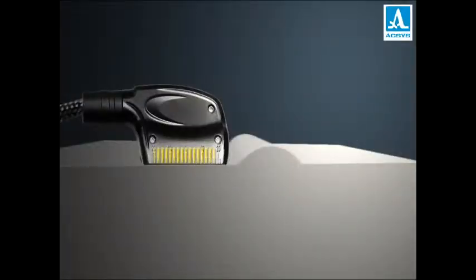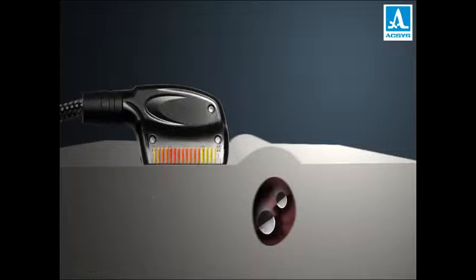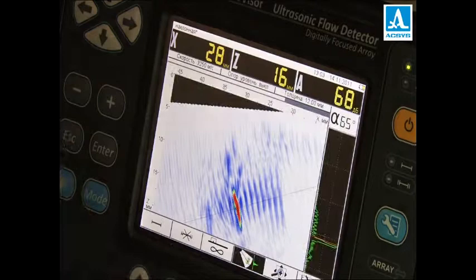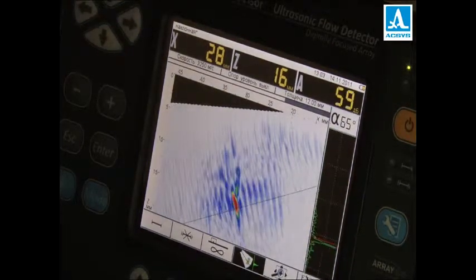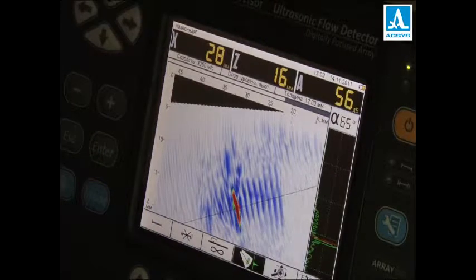The antenna array of the IntroVisor is a group of 16 elements. Each of them in turn emits an ultrasonic pulse, while all the rest receive echo signals with varying delay times. There is no physical focusing or synchronization of pulses. As a result of each pulsing cycle, 136 independent echograms are saved to the memory.